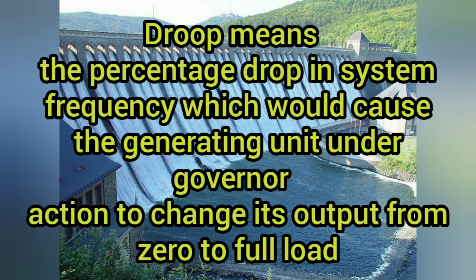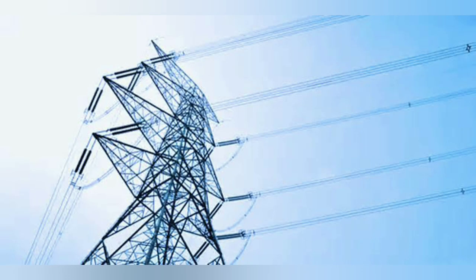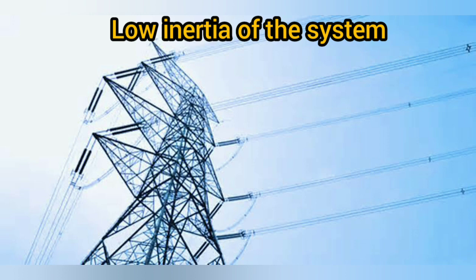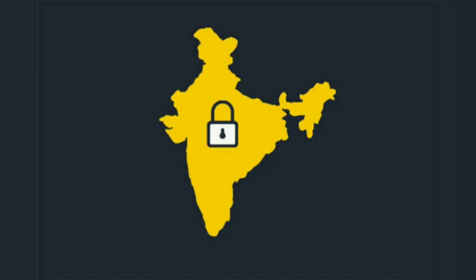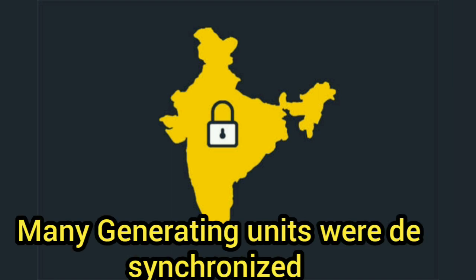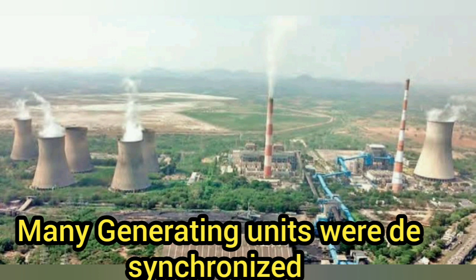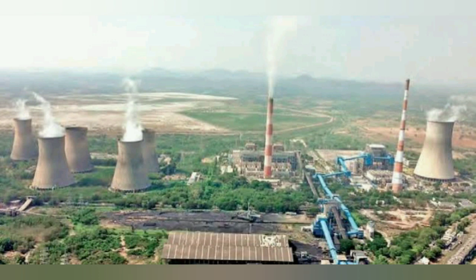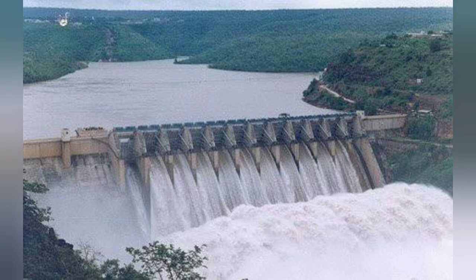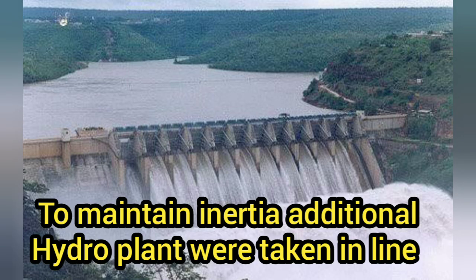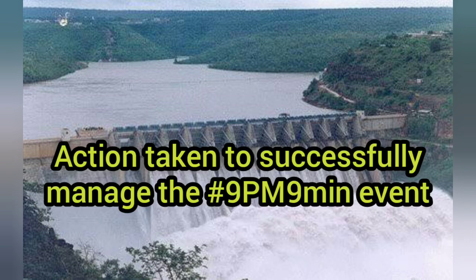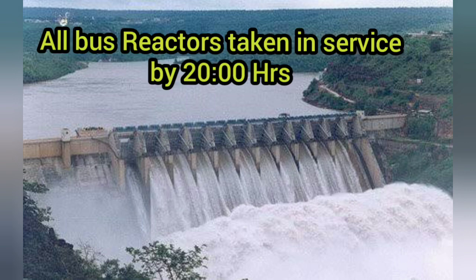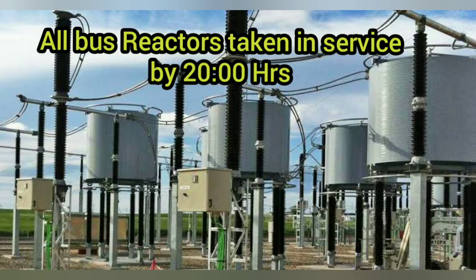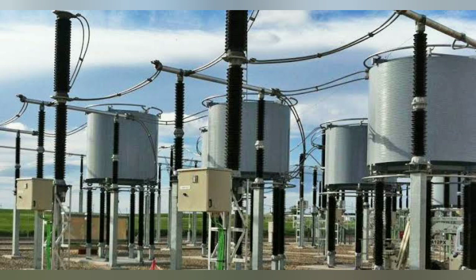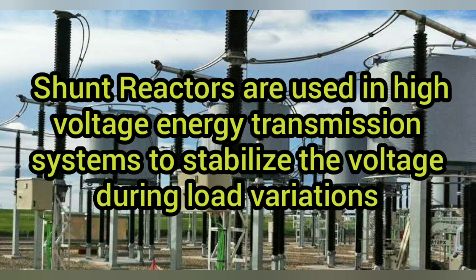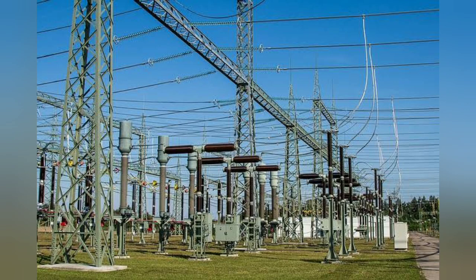One major concern in arresting significant variation in grid frequency during the event was the low inertia of the system. Since the countrywide lockdown on 25th March 2020, many generating units were desynchronized from the grid, causing a significant reduction in system inertia. So to take care of this, additional hydro and gas units were brought along with the load-based thermal power. Now I will tell you the actions that were taken. First, all bus reactors would be taken into service by 20:00 hours if voltages are slightly lower than 1 pu at 400 kV and above voltage level nodes. A list of lines which could be further opened without loss of reliability was prepared.